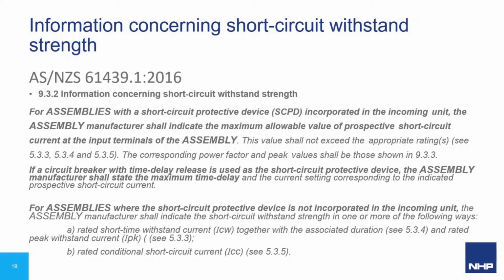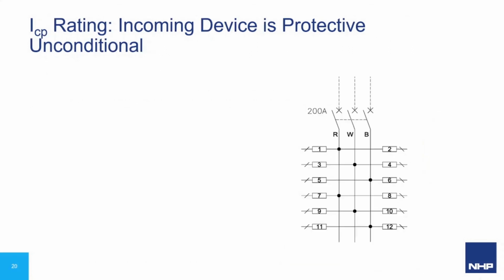The other rating they can choose when the protection device is upstream to the assembly is the conditional withstand rating. This is the best of both. A specific upstream protection device is nominated, which the assembly manufacturer refers to. This will typically give the most economical solution. We will have a closer look at these three ratings before we look at some practical examples.